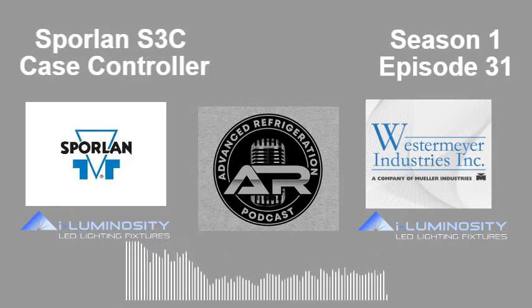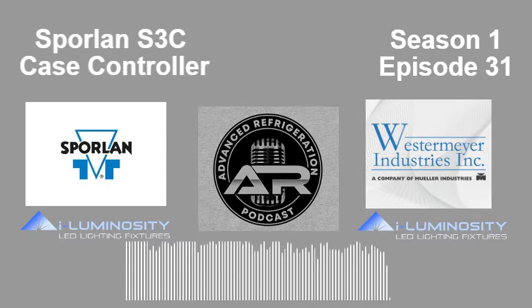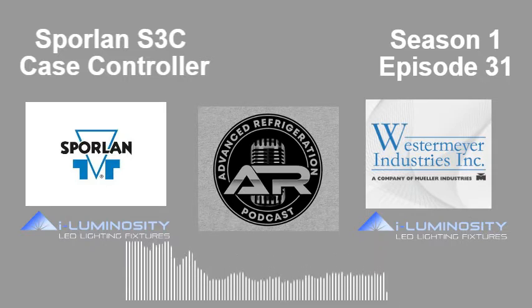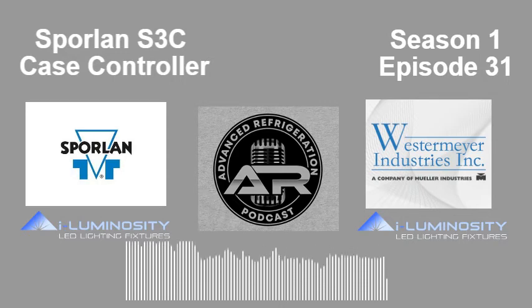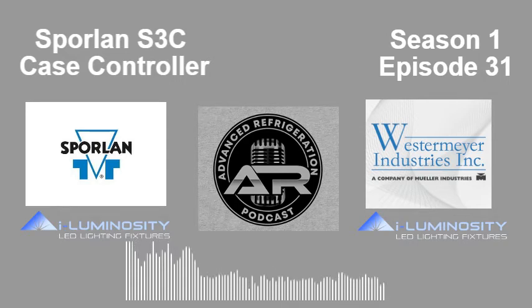One question that has befuddled a number of us is some of the terminology, like standalone and self-contained, because this whole system was intended to stand alone without a building automation system. That's one of the set points you can select. Self-contained is another parameter. The way we've established it, it has to do with the compressor location. Is the compressor in a rack or otherwise? Remote is also a compressor location issue. Self-contained can come into play if you have a refrigerator-style appliance, with the evaporator, condenser and compressor all in one spot. All those are parameters that need to be selected.